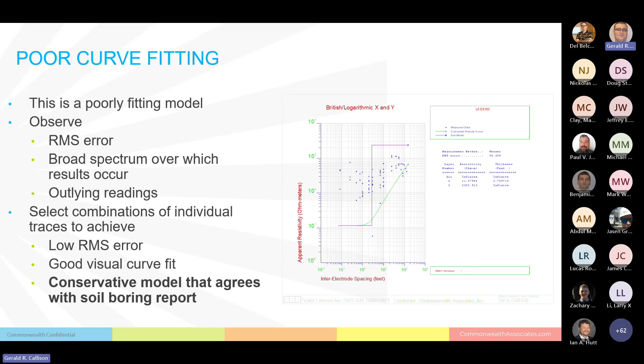What we would do is select combinations of individual traces. We would look for that RMS error to lower, to fit the curve better. We would look for numbers that were conservative, at the upper end of what we'd expect based on soil boring reports. We'll talk in depth about expectations based on soil boring reports, because that's critical to good grounding design. But that's what we'd do for such a poor curve fit. This is not something we would use.